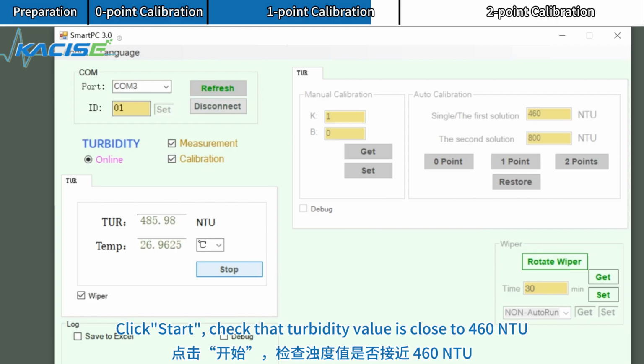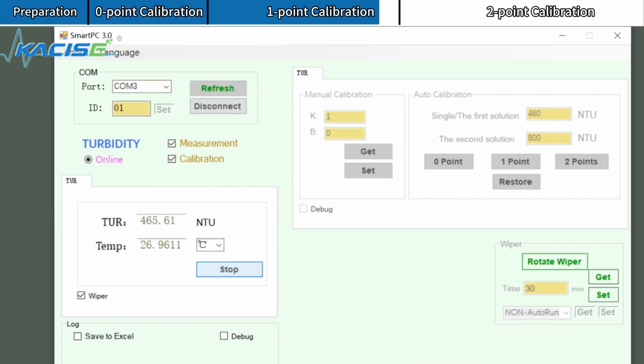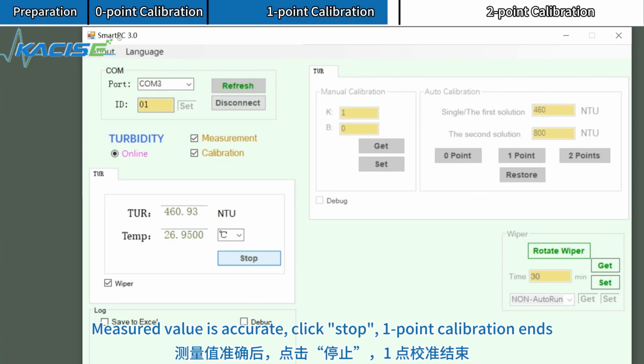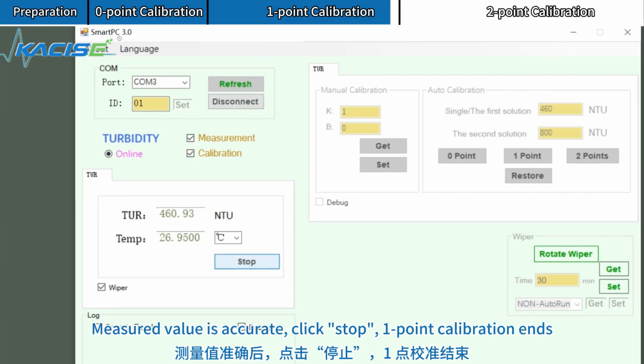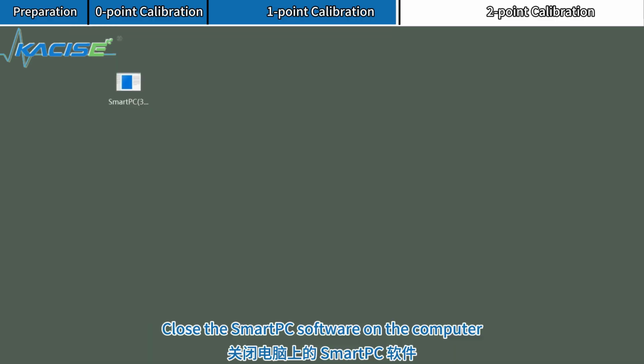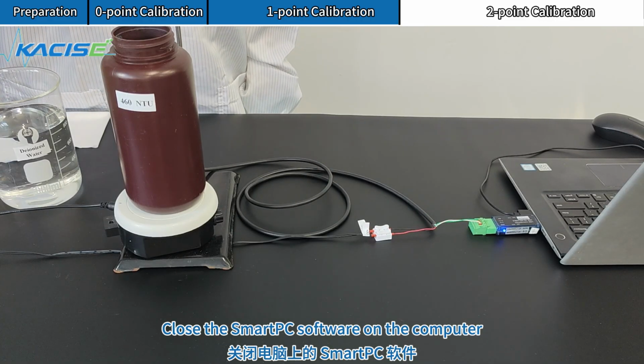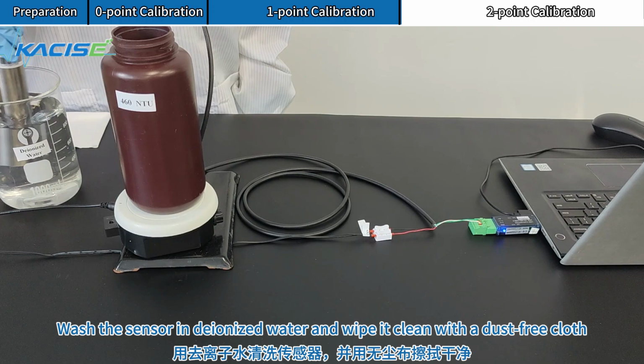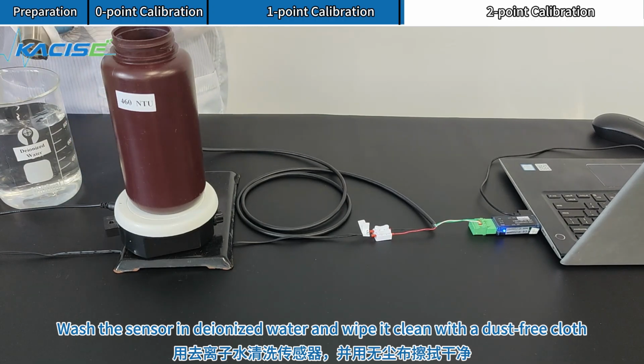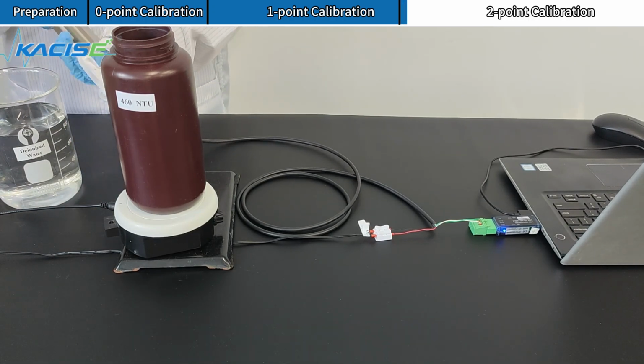Click Start. Check that turbidity value is close to 460 NTU. Measured value is accurate. Click Stop. 1 point calibration ends. Close the Smart PC software on the computer. Wash the sensor in deionized water and wipe it clean with a dust-free cloth.